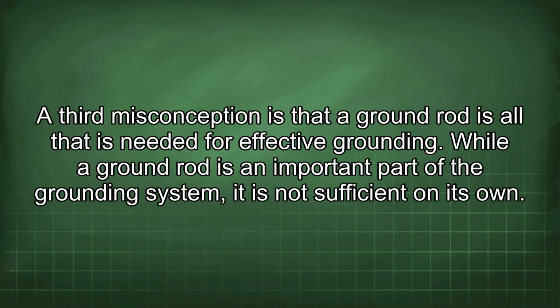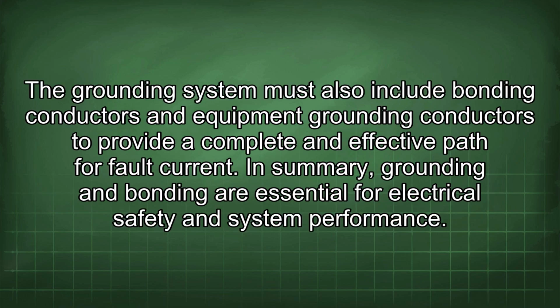A third misconception is that a ground rod is all that is needed for effective grounding. While a ground rod is an important part of the grounding system, it is not sufficient on its own. The grounding system must also include bonding conductors and equipment grounding conductors to provide a complete and effective path for fault current. In summary, grounding and bonding are essential for electrical safety and system performance.